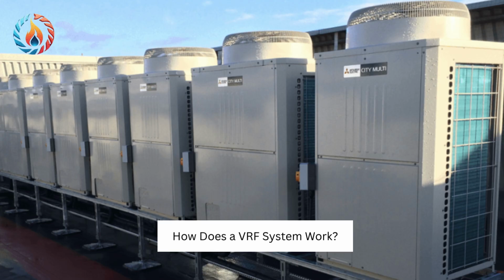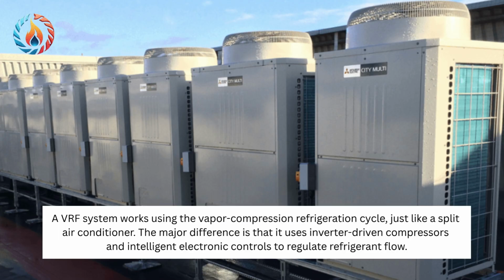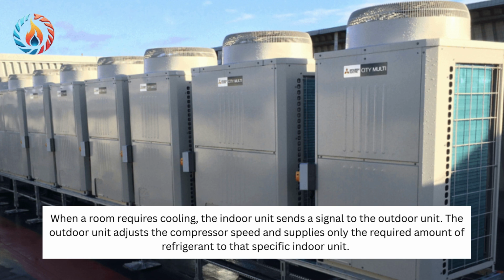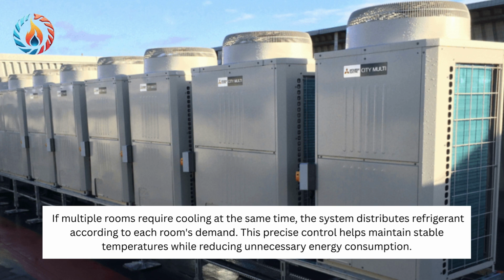How does a VRF system work? A VRF system works using the vapor compression refrigeration cycle, just like a split air conditioner. The major difference is that it uses inverter-driven compressors and intelligent electronic controls to regulate refrigerant flow. When a room requires cooling, the indoor unit sends a signal to the outdoor unit. The outdoor unit adjusts the compressor speed and supplies only the required amount of refrigerant to that specific indoor unit. If multiple rooms require cooling at the same time, the system distributes refrigerant according to each room's demand. This precise control helps maintain stable temperatures while reducing unnecessary energy consumption.